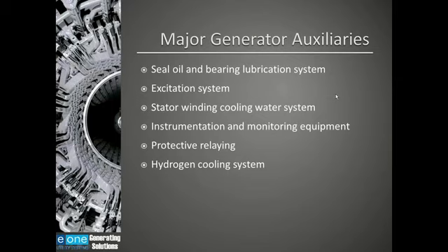Some major components or generator auxiliaries are the seal oil and bearing lubrication system, the excitation system. If it's a generator with a water-cooled stator, there's a stator winding cooling water system. Some people will refer to the instrumentation and monitoring equipment as an auxiliary system. You have protective relays for the generator. And then you have the hydrogen cooling system, and that's what we're going to be discussing in this presentation.